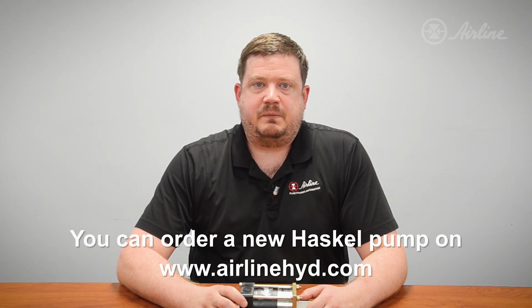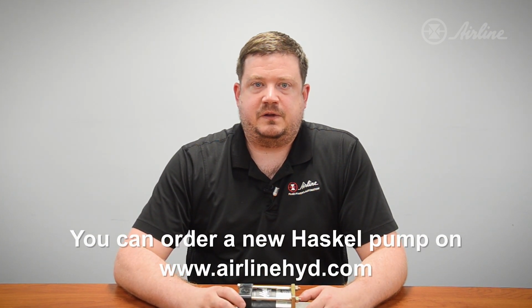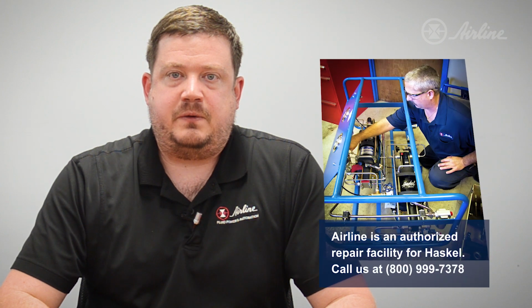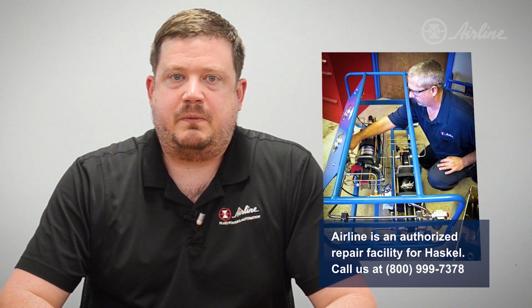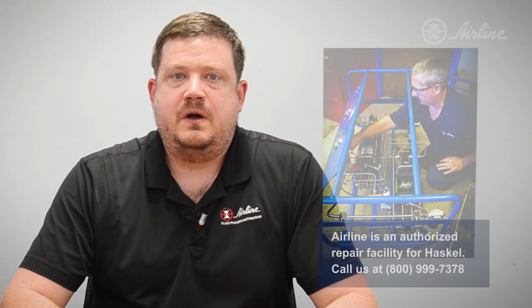Luckily, this pump series is inexpensive, so you can find a replacement for around $800 at list price. But if you're proactive with fixing your pump, you have a few other options. You can take it to a Haskel repair center, where the repair price will be around $400, or you can buy the seal kits for under $200 and rebuild the pump yourself. To me, the most cost-effective solution is to replace the seals yourself. And if you follow this tutorial, you'll find it's fairly easy and you'll be up and running in no time.